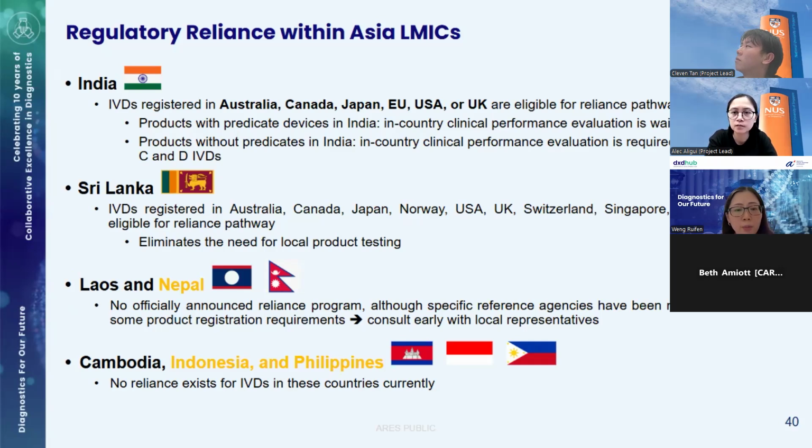But it's important, I think helpful, to also note that in the event that there is no predicate in the Indian market, even if a product has been pre-registered in the Reliance markets, the Indian authorities will still require in-country clinical performance evaluation for class B, C, and D IVD products.